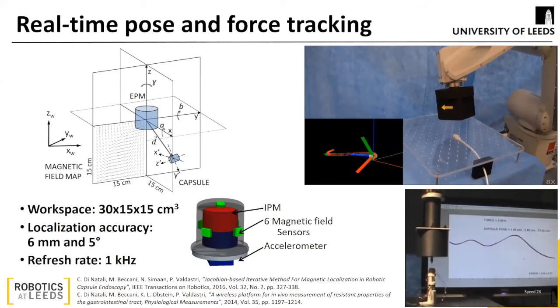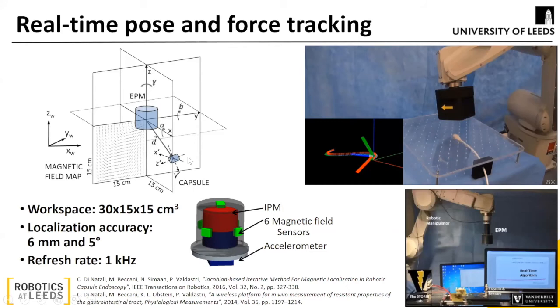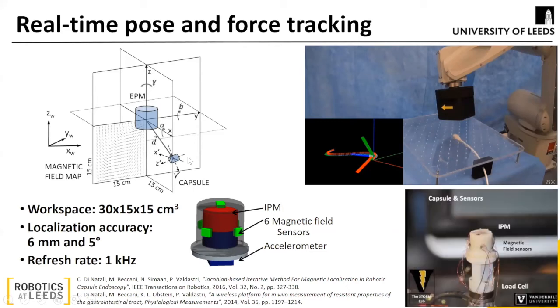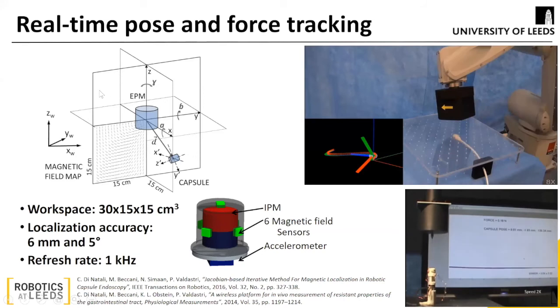Then we perform a search in a pre-calculated magnetic field map that gives us the position that the tip should have to read these values for the external field. Since the external magnet is a cylinder, magnetized along its main axis, its field presents an axial symmetry. This greatly reduces the search space, allowing the pose tracking algorithm to run at 1 kHz.